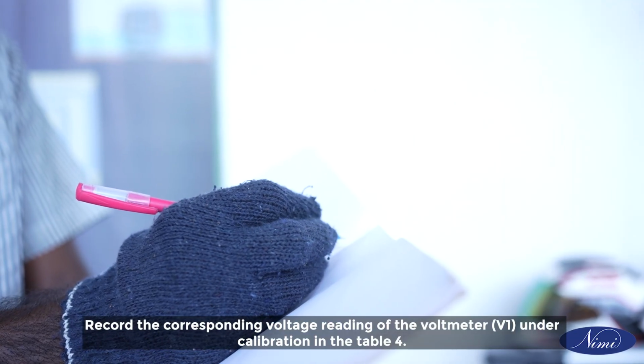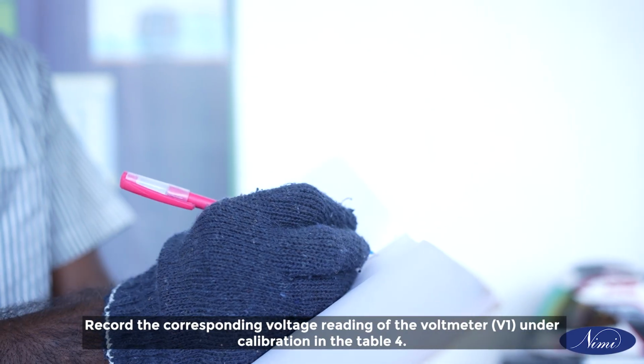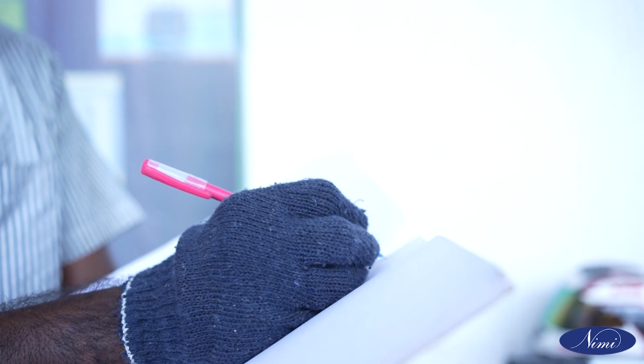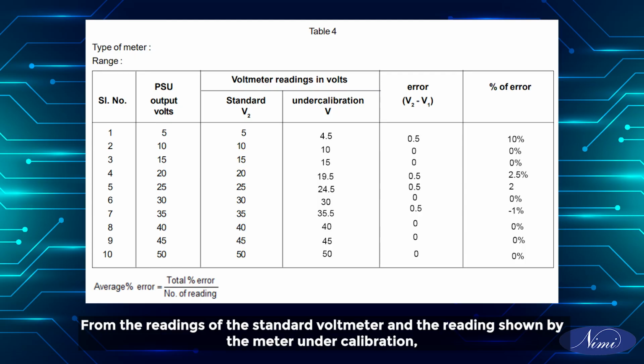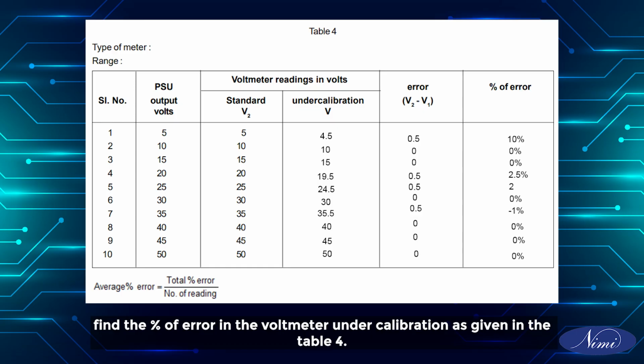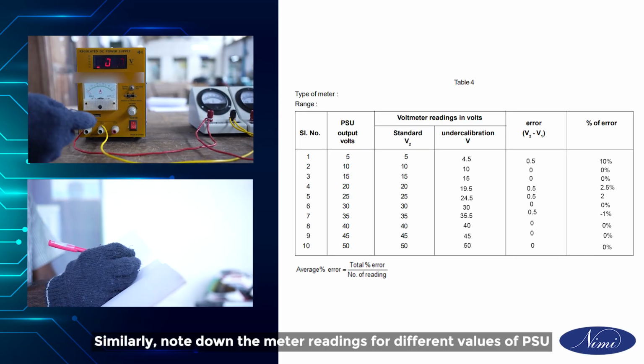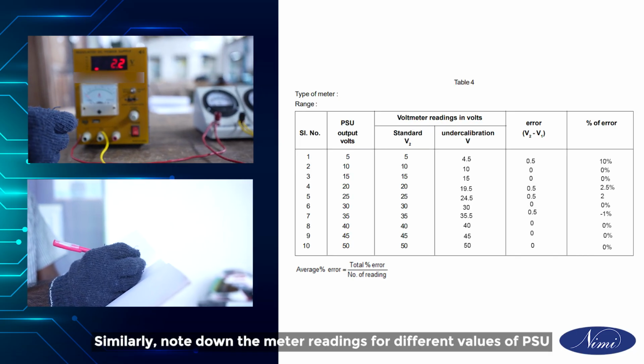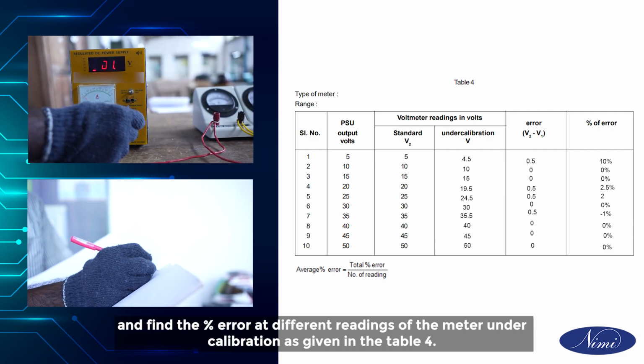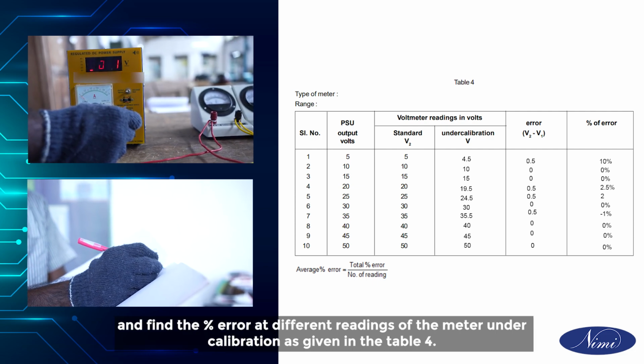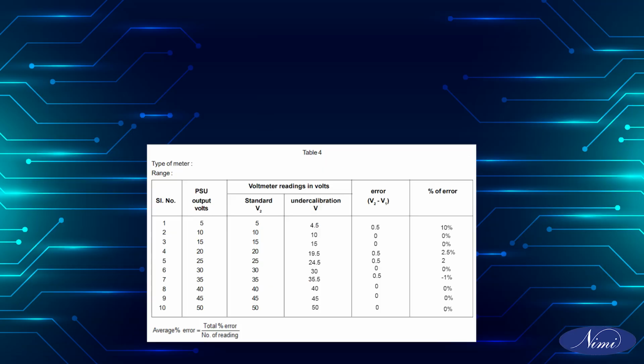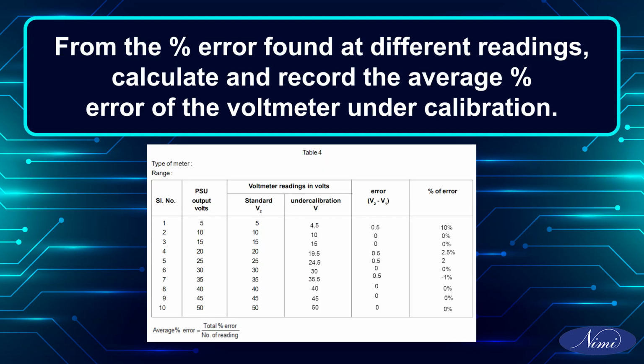Record the corresponding voltage reading of the voltmeter, V1, under calibration in table 4. From the readings of the standard voltmeter and the reading shown by the meter under calibration, find the percent of error in the voltmeter under calibration as given in table 4. Similarly, note down the meter readings for different values of PSU and find the percentage error at different readings of the meter under calibration as given in table 4. From the percentage error found at different readings, calculate and record the average percentage error of the voltmeter under calibration.